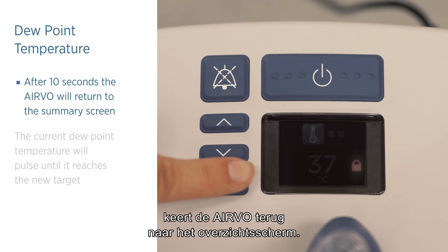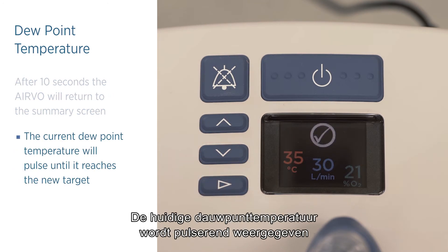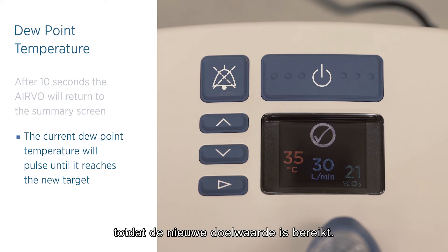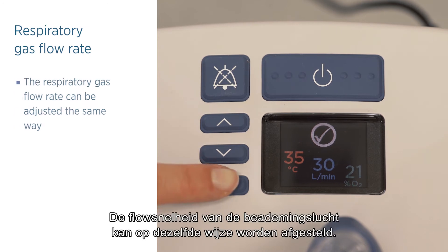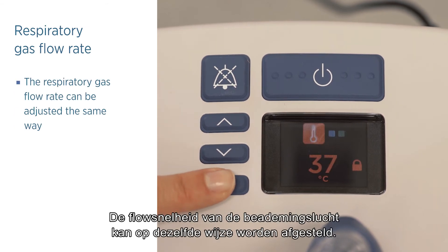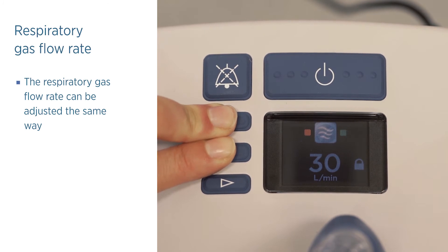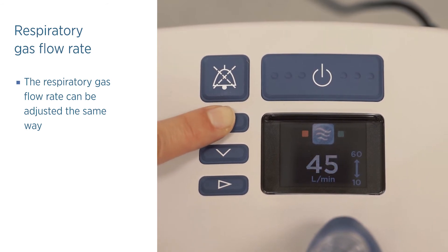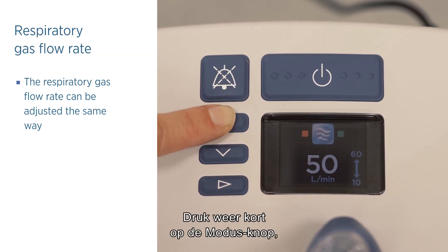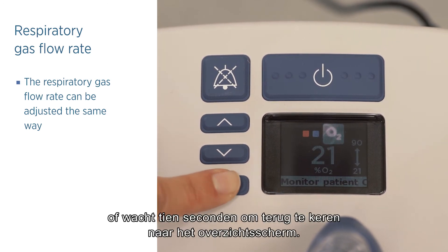After 10 seconds, the AIRVO will return to the summary screen. The current dew point temperature will pulse until it reaches the new target. The respiratory gas flow rate can be adjusted the same way. Press and release the mode button again or wait 10 seconds to return to the summary screen.